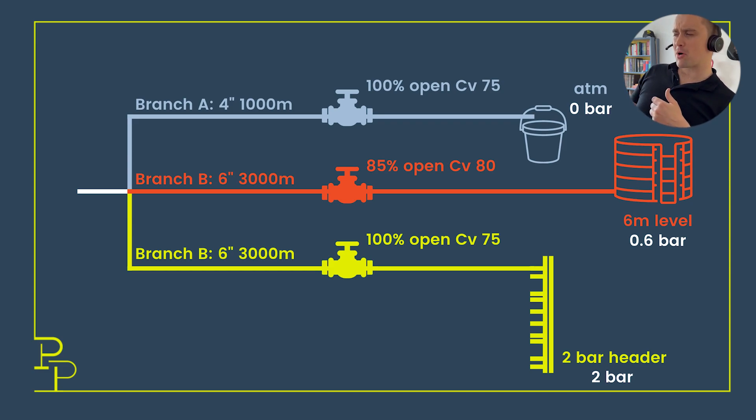If you're saying downstream I don't have a fixed constant pressure, I actually have an exchanger, a reactor, all sorts of things happening there, then I'd say to you that branch is not fully defined. Until the point where you can get to a constant pressure or you can define the exact flow rate in that branch, you need to further define the system curve for that individual branch by itself.